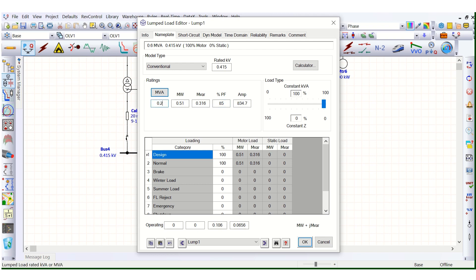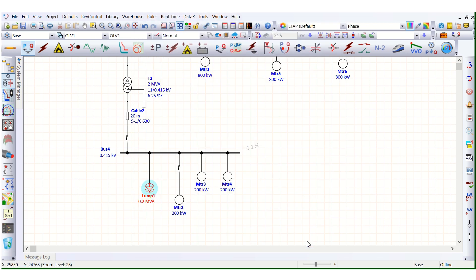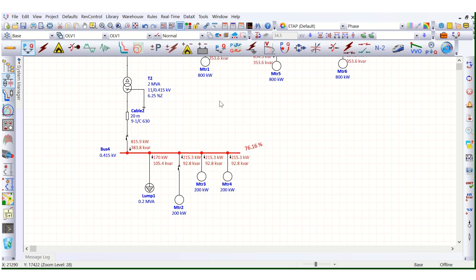If we change the load to 0.2 MVA, the load is now reduced. Let's run the load flow once again. The error is now removed.